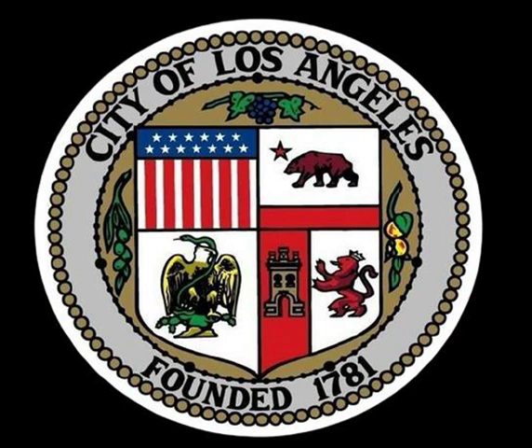Our first responders, our patrolmen, went out and identified where the fire was and what the threats were as it moved into our overhead distribution area. They ordered these circuits de-energized at the time. This particular circuit's station does not have the ability to shut off individual circuits one at a time, so they requested the whole distribution station de-energized, which de-energized the entire area while they sectionalized and slowly brought them back on after the fire had burned through.